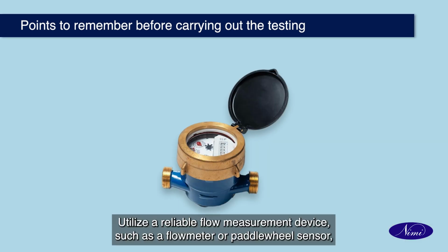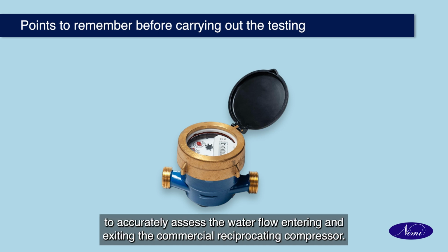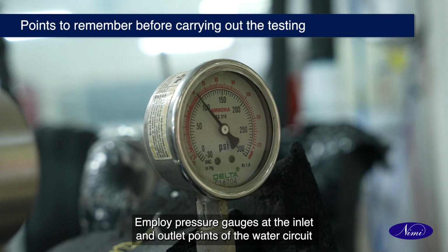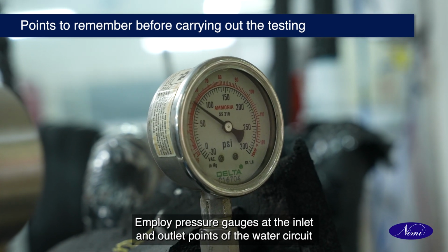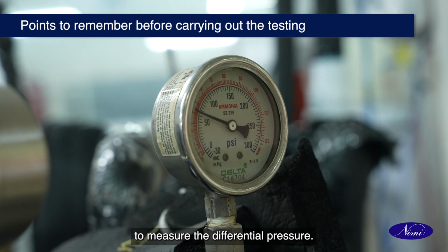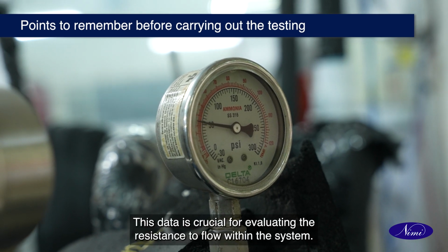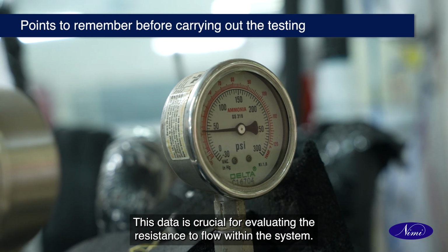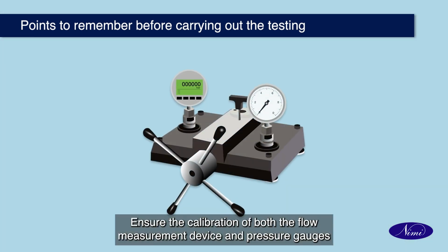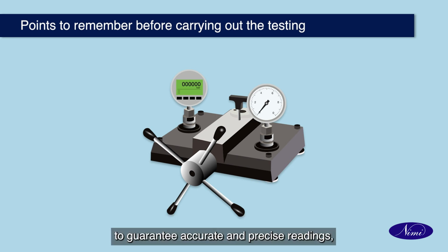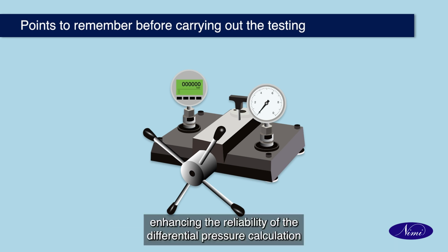Utilize a reliable flow measurement device such as a flow meter or paddle wheel sensor to accurately assess the water flow entering and exiting the commercial reciprocating compressor. Employ the pressure gauges at the inlet and outlet points of the water circuit to measure the differential pressure. This data is crucial for evaluating the resistance to flow within the system. Ensure the calibration of both the flow measurement device and pressure gauges to guarantee accurate and precise readings, enhancing the reliability of the differential pressure calculation.